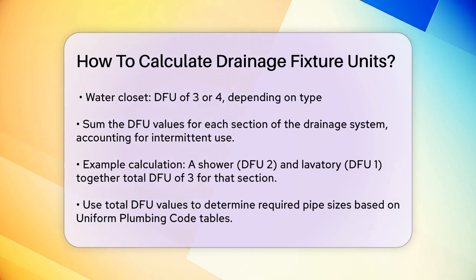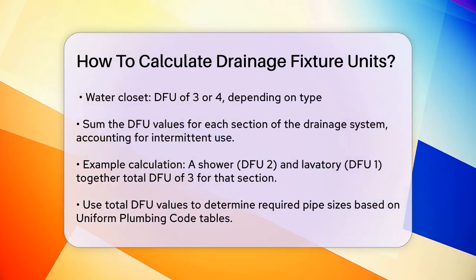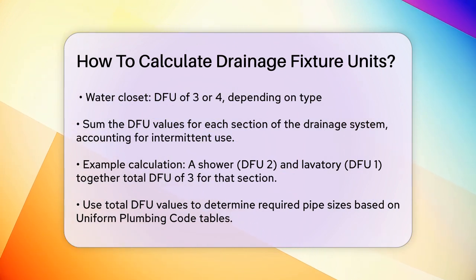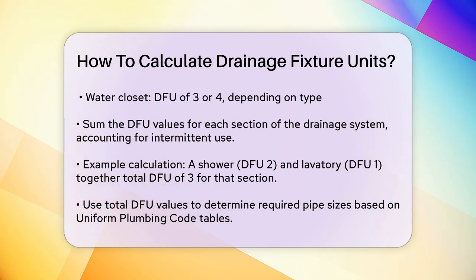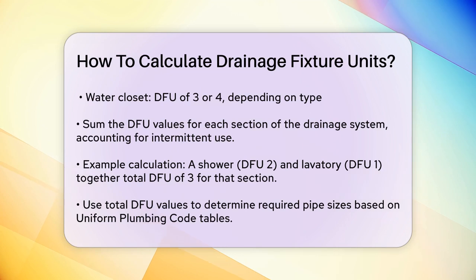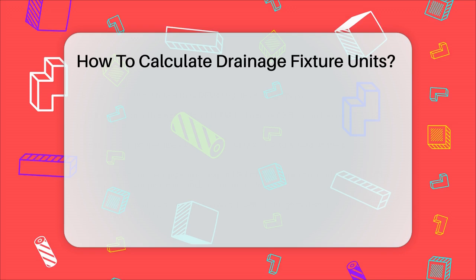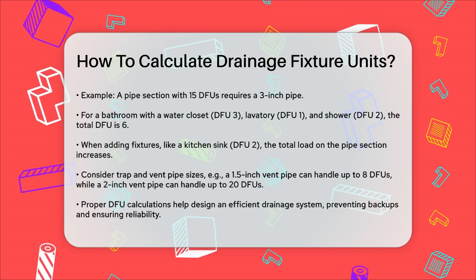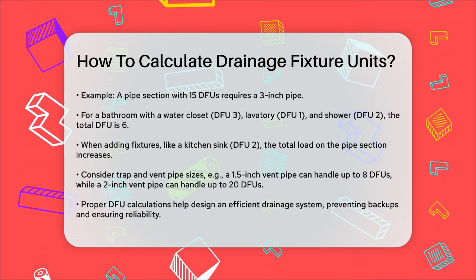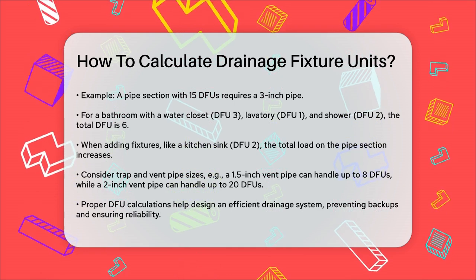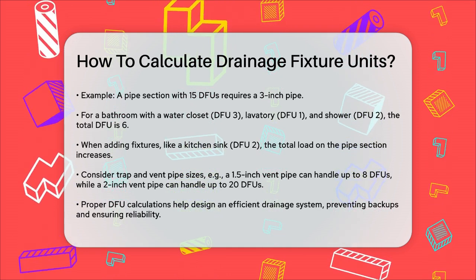Here's a practical example. If you have a bathroom with a water closet — DFU of three — a lavatory — DFU of one — and a shower — DFU of two — the total DFU for this bathroom would be six. If this bathroom is connected to a pipe that also serves another fixture, say a kitchen sink with a DFU of two, you would add these values together to get the total load on that pipe section.